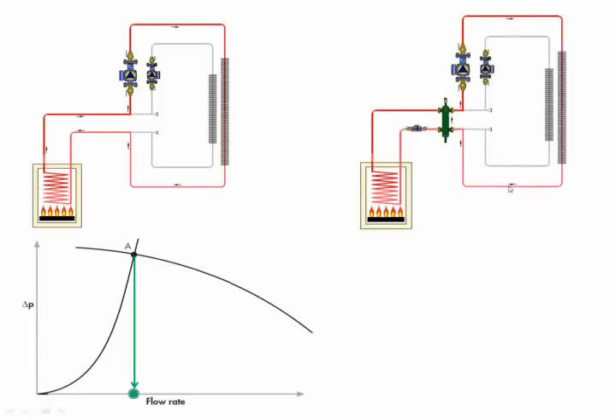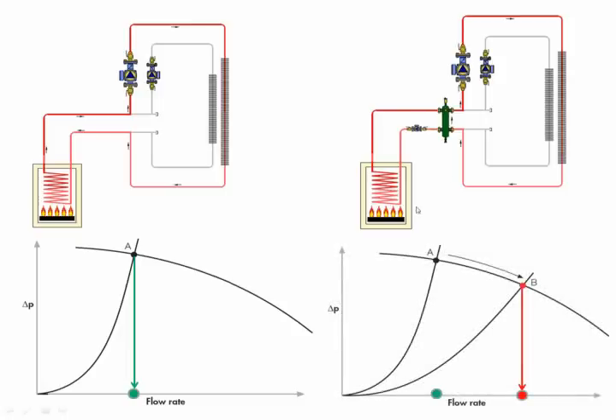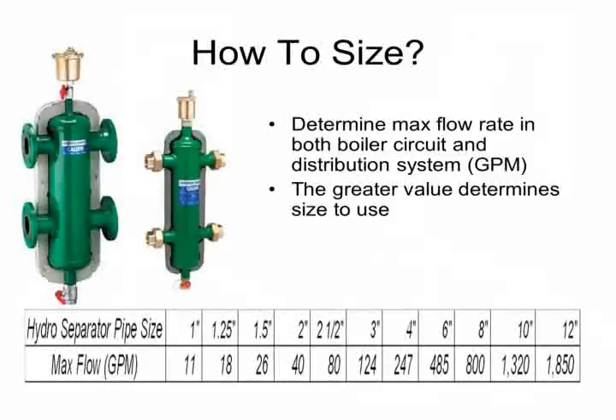When we introduce a hydraulic separator now, it changes things. That curve now has been flattened out because what? We've reduced the resistance that pump has to see, okay? So rather than flowing here, that same pump would cause it to flow here. So hydraulic separation also enables smaller pumps to be used most optimally.